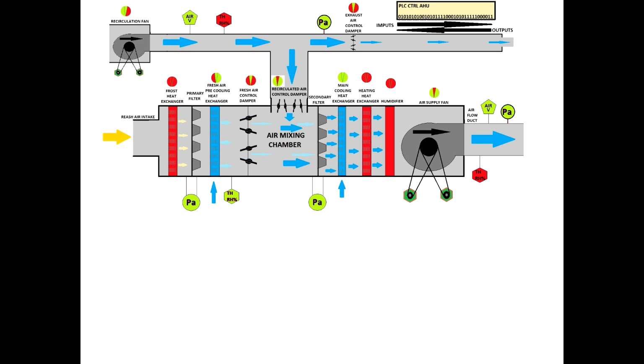Once the temperature is reached, the relative humidity and the temperature probe should change to green. That means you have a perfect condition. In case the relative humidity goes too high, you will use the heater against the cooler to balance the capacity that way, so you can run the cooler mode to remove the absolute humidity. And all these little heat exchangers will be used against each other to have a perfect control, not only in temperature but also in humidity.